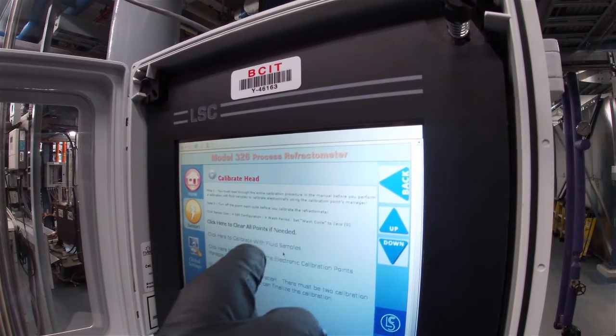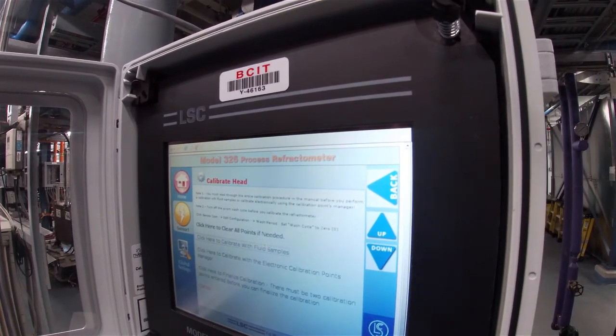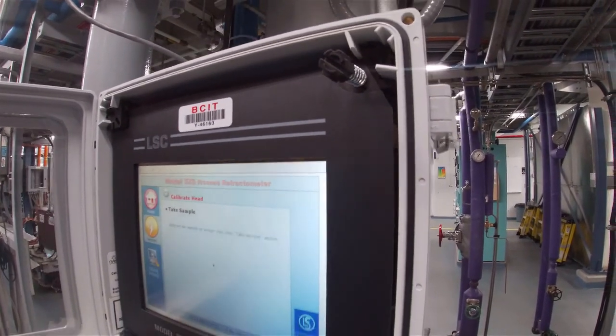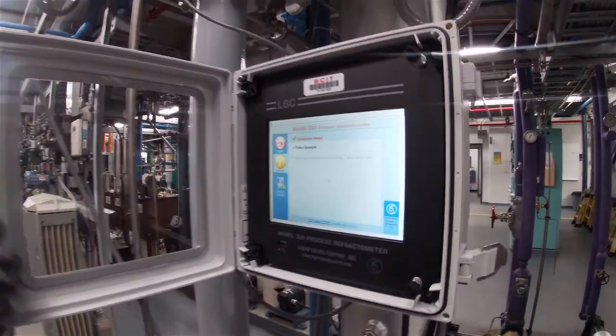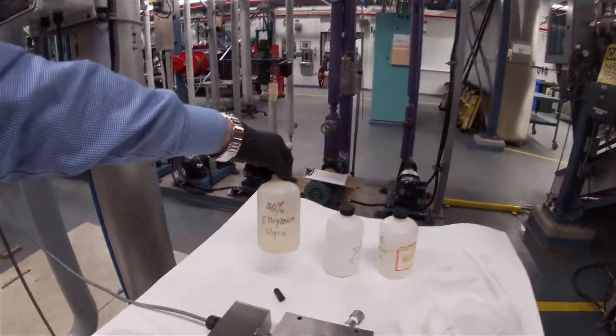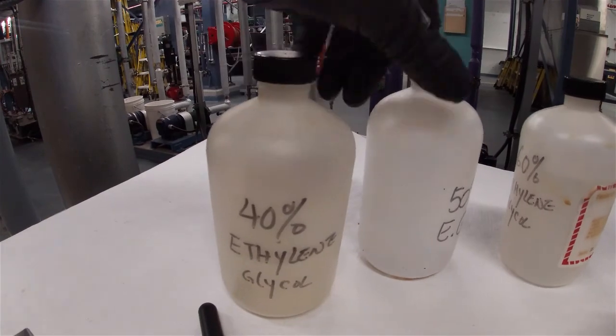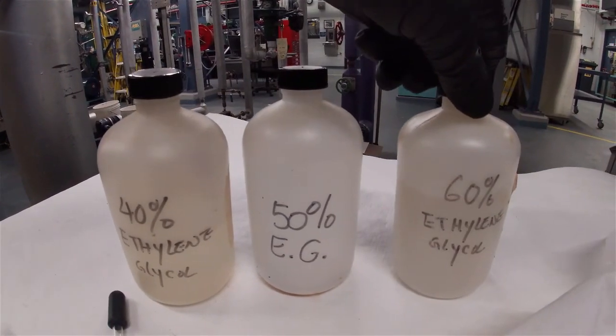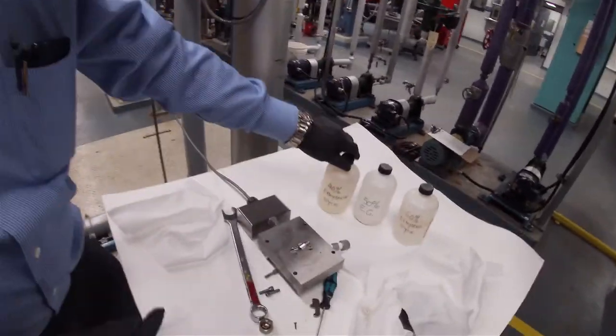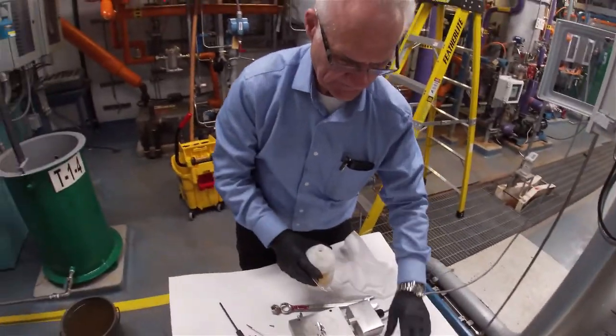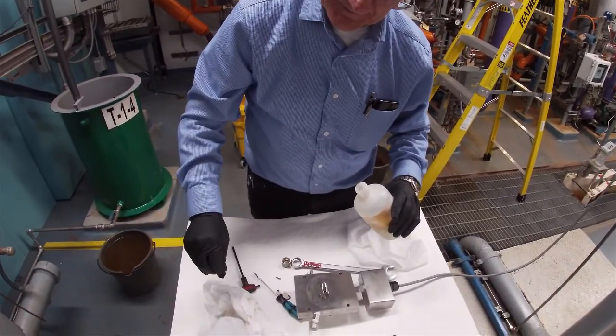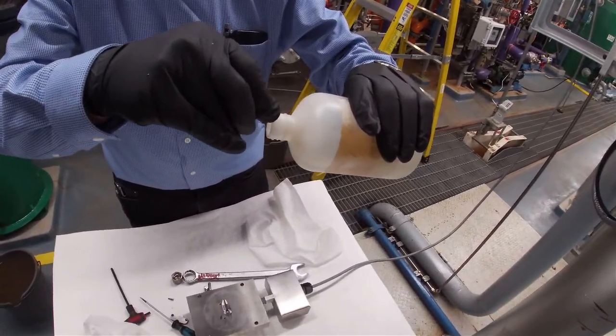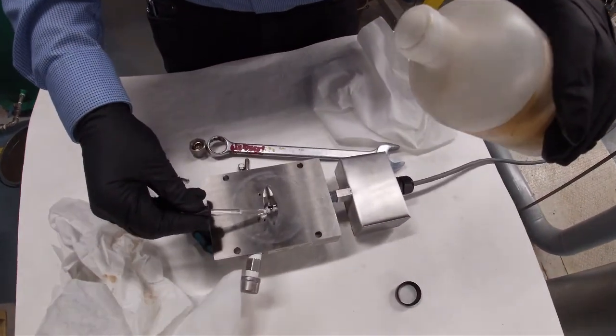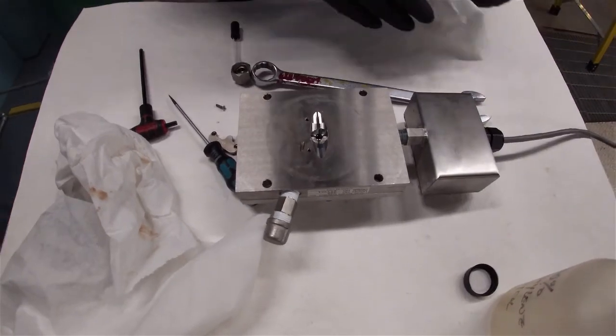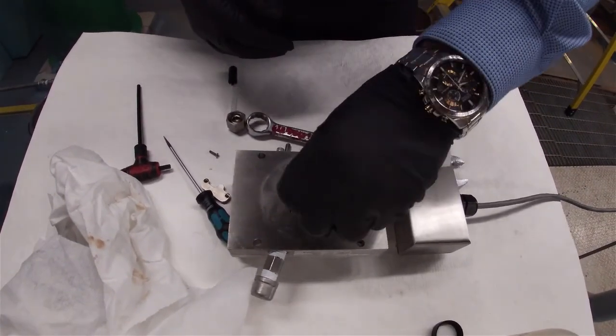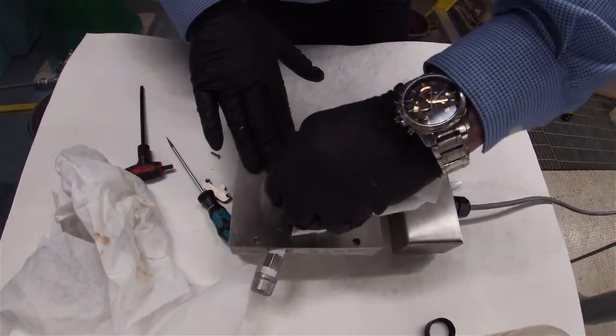Okay, so it says apply a known sample, then click take sample above. The samples that we're going to do, we've got 3 of them here: 40% ethylene glycol, 50% ethylene glycol, and 60% ethylene glycol. We're going to start with the 40. Make sure that there's nothing in the eyedropper. I'm going to take a sample and put it on the window. Then I'm going to wipe the window off with that sample, so that it makes sure there's no residual from whatever was in there before left on the prism itself.